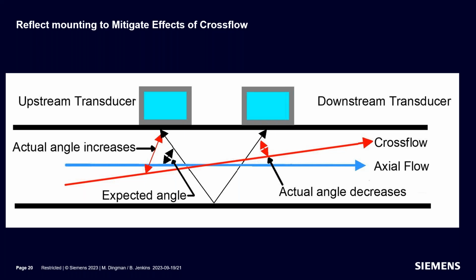And this is one reason why a clamp-on meter has advantages over a wetted meter. People will think that, oh, well, if I have transducers inserted through the pipe wall and touching the fluid, that's a more accurate measurement. And that's a better way to measure. And it's absolutely not. A clamp-on meter will only need half the number of transducers of an insert meter because an insert meter is always in direct mount. So this error would affect an insert meter, and unless they put the same number of transducers pointing in the opposite direction, they're going to have a big error. So a dual path clamp-on meter would be the equivalent of a 4-path wetted meter. So they would need 4 sets of transducers. A 4-path ultrasonic clamp-on meter would be the same as an 8-path wetted meter.